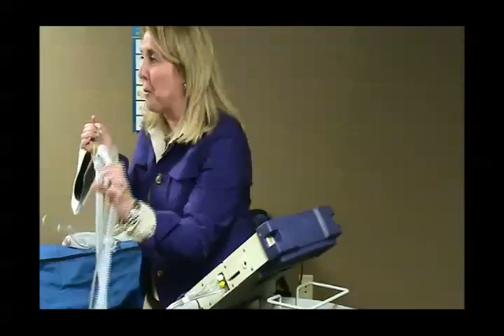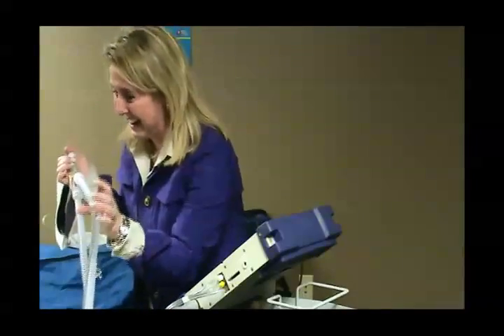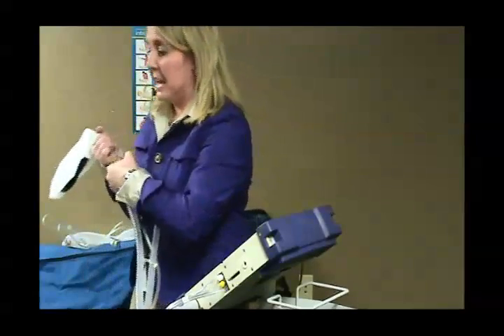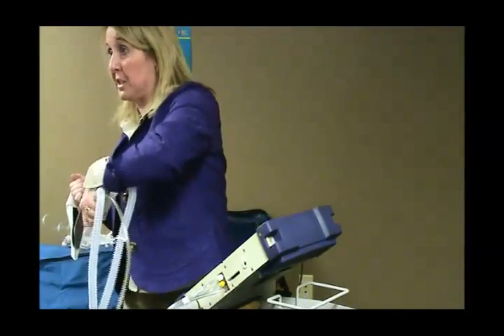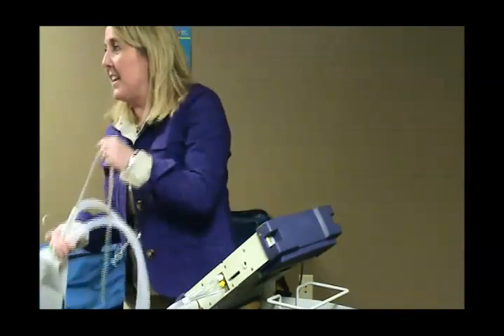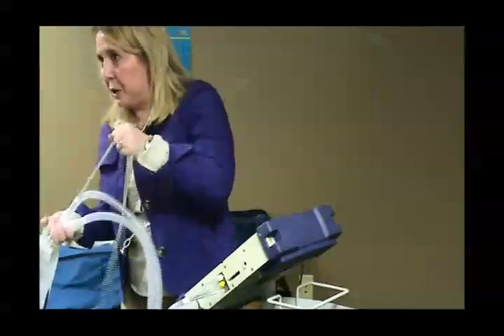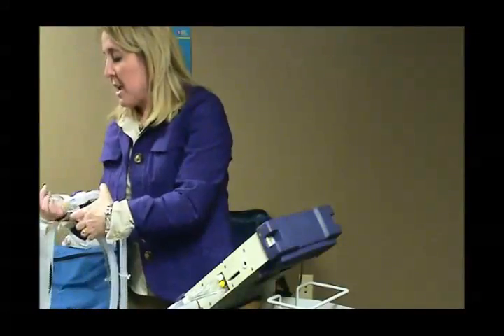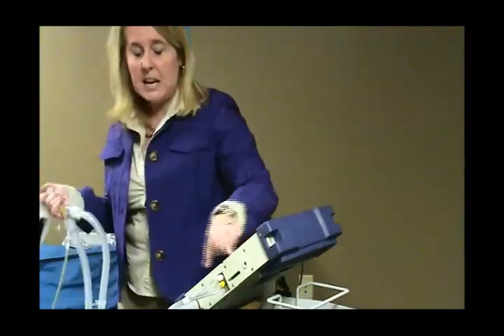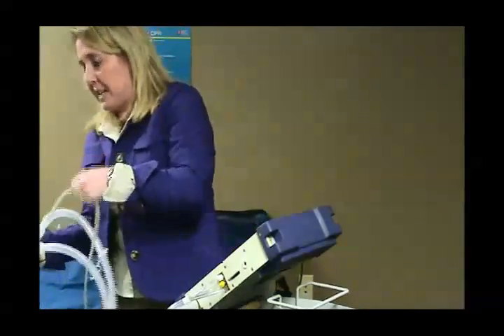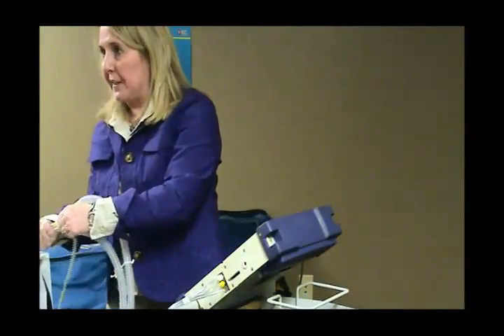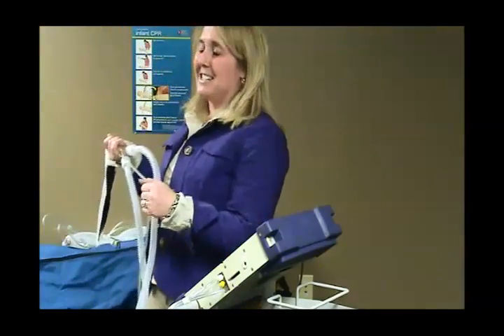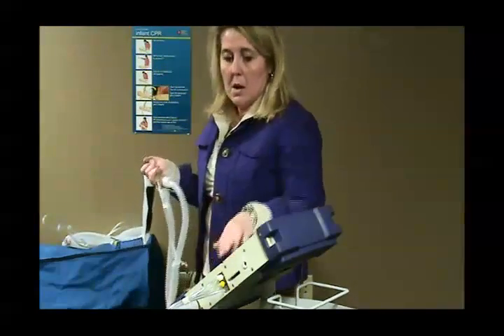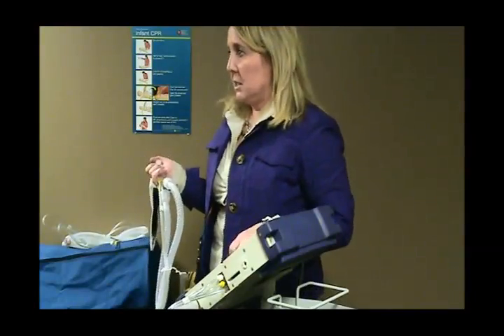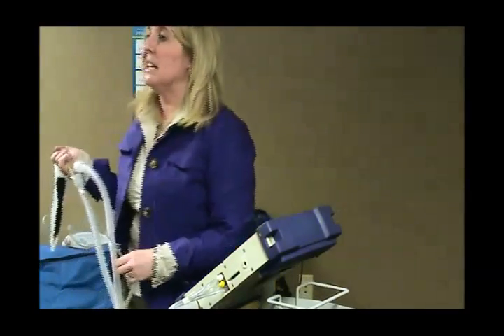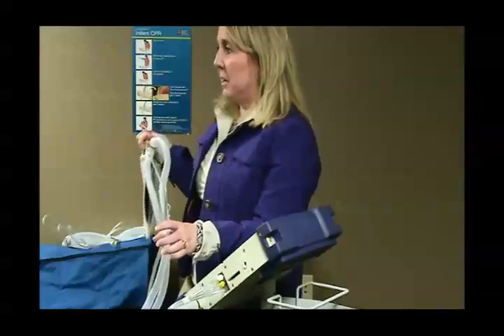So the question just came up, what do I do if there's water in there? How do I get it out? Well, this is one of the only times that you disconnect from the patient and go towards the end of the circuit. If you can get it out of there by sort of trying to squeeze it away from there, then you want to do that. You can tap it out. Sometimes you can squeeze it out of there a little bit. You see a water droplet in there, you can get it out. If you can't get it out, you have to change the circuit. It does not mean that the circuit is bad. It means that water was in it.